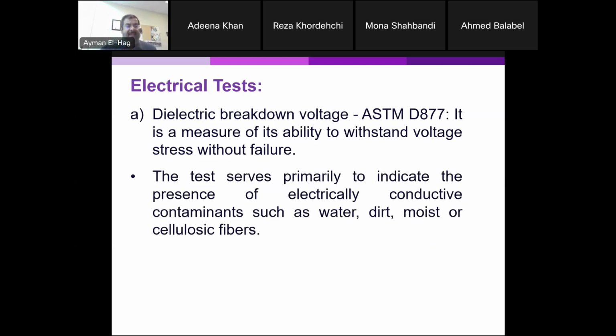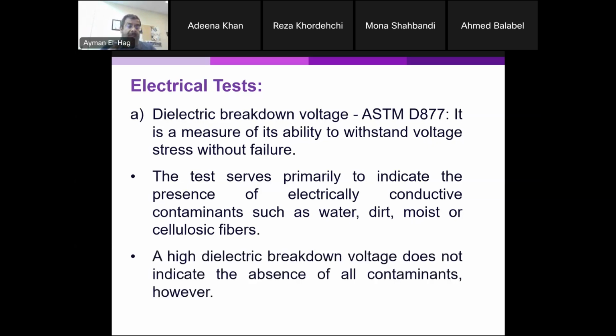So it's an indication, of course, obviously, that when the breakdown voltage goes down, it means that there are some conductive contaminants, such as water, dirt, moisture, or even some cellulose fibers that bridge the gap between the two electrodes and cause the flashover to happen. So for this test, the higher the breakdown, the better the transformer oil. However, and this is also from experience, if you have oil with a high breakdown voltage, that does not mean that the oil is good. And I have seen some samples of oil, very dark in color, meaning that there is a lot of contamination and/or oxidation happening to the oil, so it's not really a good oil, but still the breakdown voltage is relatively high.